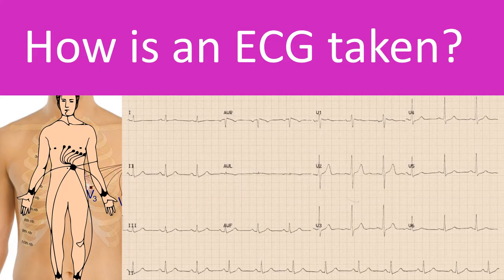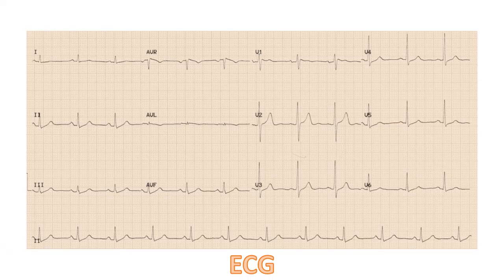ECG is short for electrocardiogram — the recording of the electrical activity of the heart. It is recorded by placing metallic contacts known as electrodes in specified parts of the limbs and chest, connecting them to the ECG machine known as an electrocardiograph. The electrical signals from the heart detected on the surface of the body are tiny, in the range of millivolts. The ECG machine amplifies these tiny signals and records the variations with time on a moving graph paper.